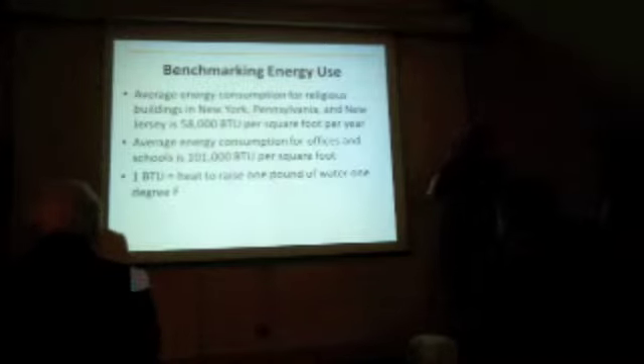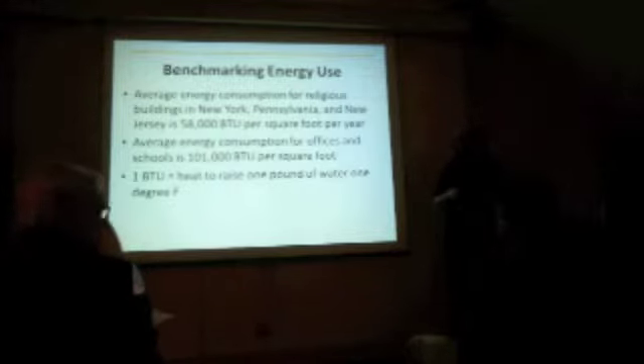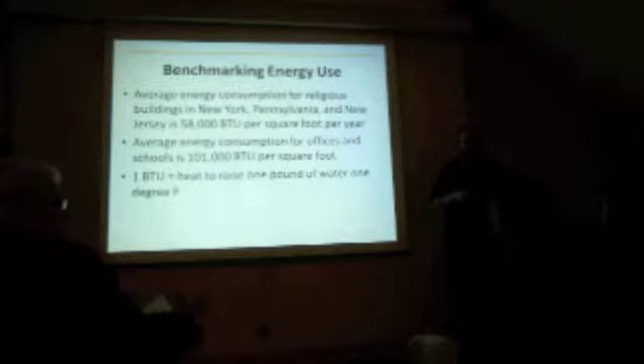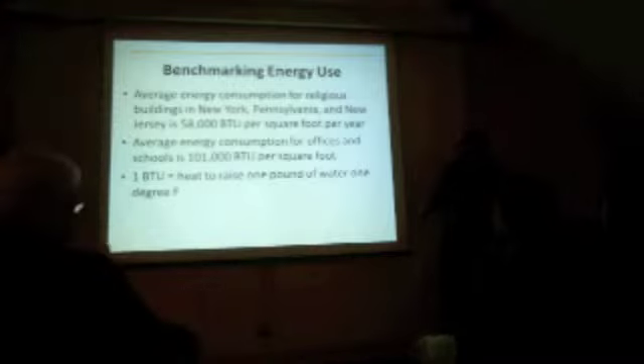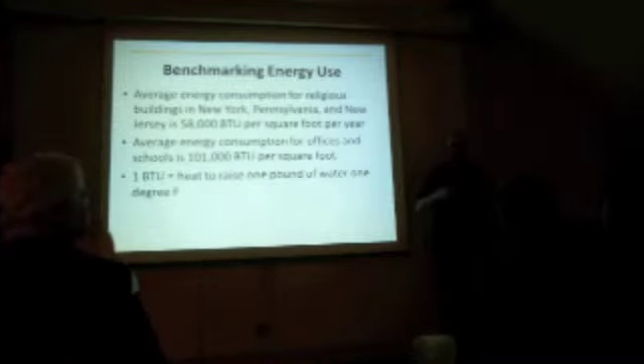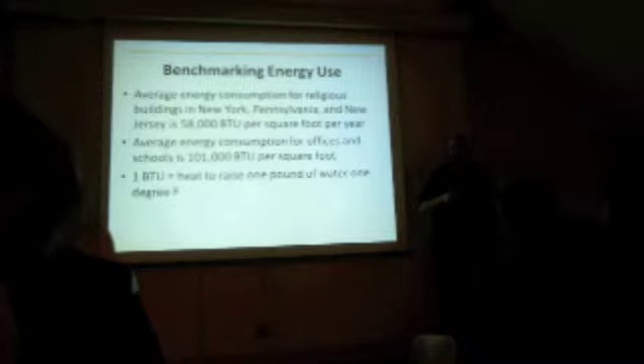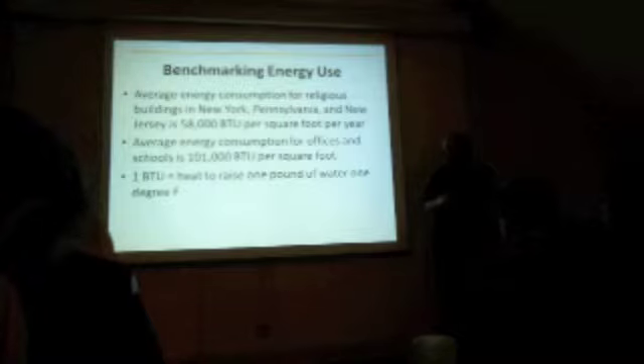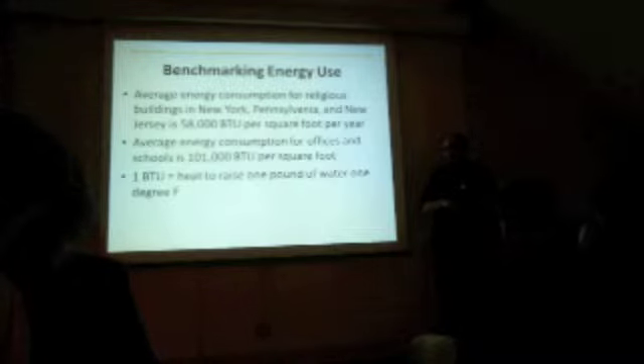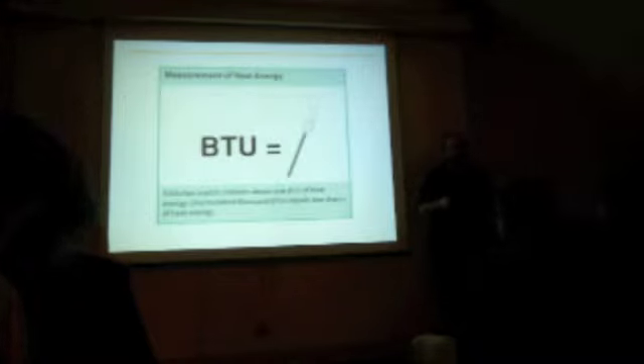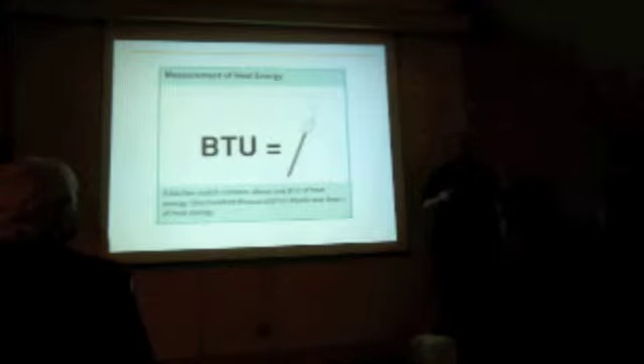So typical religious buildings in our climate zone, they lump New York, Pennsylvania, and New Jersey together as one block, use about 58,000 BTU per square foot, and a little less than twice that for an office building or a school. The BTU is the British thermal unit, so like everything else in the US, we're stuck with the old English unit. The British thermal unit is the amount of heat needed to raise 1 pound of water 1 degree Fahrenheit. Most of our energy use in these buildings is going to be connected to heating, and so we usually use the heating unit. A simple way to think of it is a BTU is about the heat energy in one kitchen match. And so that's why that number is so big, right? 58,000 BTUs per square foot per year. A single BTU is not a whole lot of energy.